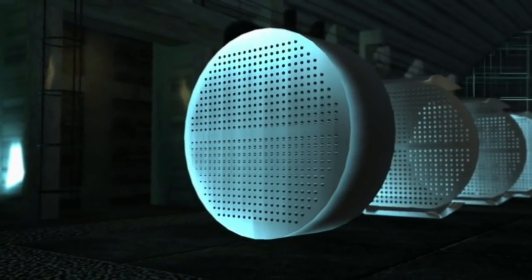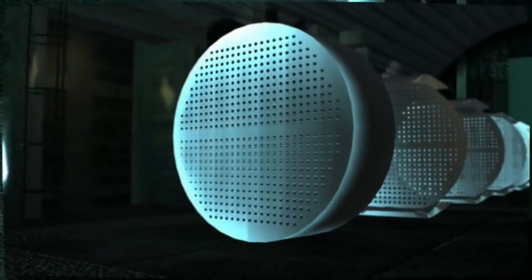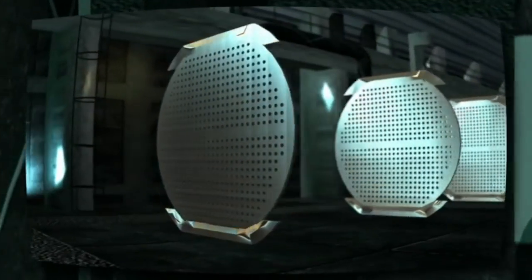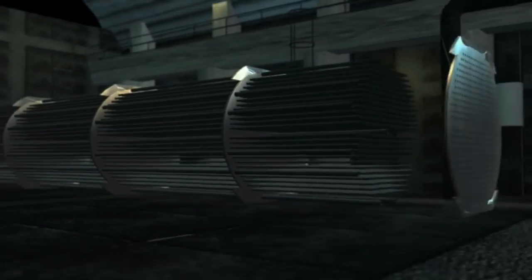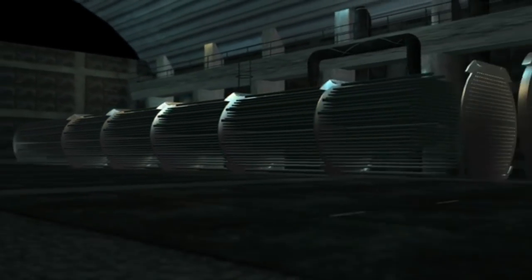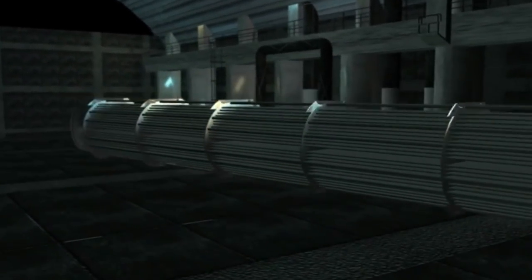We give it the utmost attention at the design and the fabrication stage. The tube to tube sheet joint apart, we place emphasis on the baffle holes because most of the failures are due to vibration.